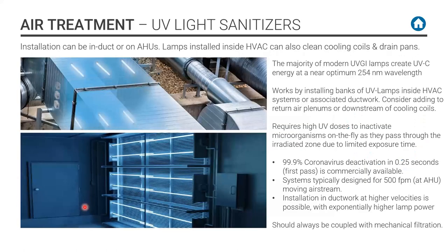So for example, in the healthcare industry, here's an illustration. This is a cooling coil and you can see the lights. These are the UV lights. We've been using these in the healthcare industry for a long time, because cooling coils are always wet. They dehumidify and there's a lot of moisture on them, and it prevents the growth of molds and spores, et cetera. If you select the lights at the right intensity, maybe 1250 microwatts, we'll look at that today, it can be effective in reducing airborne viruses that go through, but you have to have the residence time.